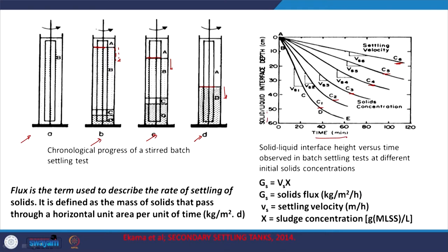The solid flux equals velocity of the interface times the concentration of that particular sludge. For design of the thickening basin there are two fluxes: one due to the underflow G1, and the other due to zone settling G2. Sludge is input at a particular rate and removed as underflow at a certain rate; thickening also occurs due to Type 3 settling at a particular rate. If the rate at which sludge is fed exceeds the total limiting flux, the interface will rise, potentially leading to overflow and unclear effluent.